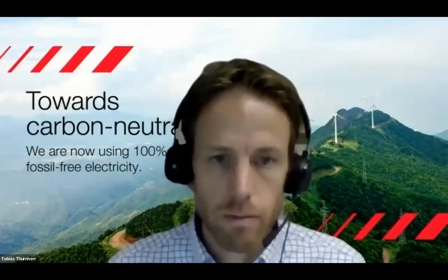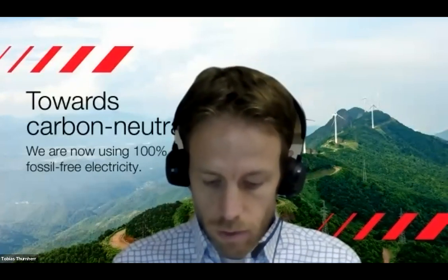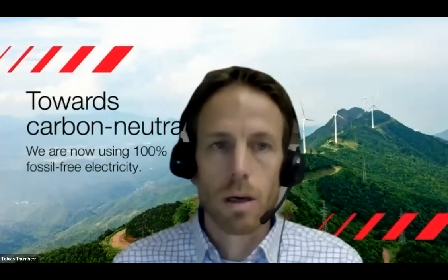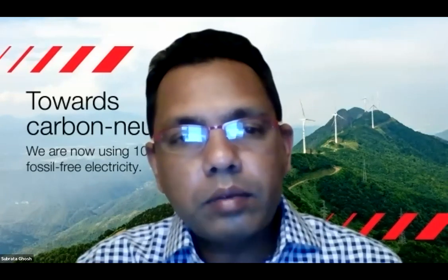We went on site, yes. People from our center of competence were there for commissioning the static frequency converter, and we are available through remote connection if there is a problem that needs support from an engineer from our center of competence. But commissioning is done with the people from our center of competence. Absolutely, the commissioning was done in conjunction with the guys from Switzerland and our UK commissioning team together. The SFC is monitored 24/7 remotely from Switzerland, which is why we have the long-term service agreement. They can log in from Switzerland and check the behavior of the SFC and what went wrong.